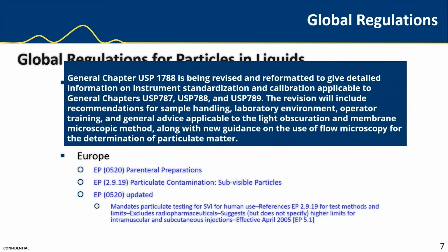So traditionally, and outlined in USP 788, for example, the testing of the system, when we say system, we're talking about the primary method, the liquid particle counter. The testing of that instrument is to occur every 6 months. So we're going from 6 months down to every time you use it, basically, to sample your product. That's a big step.